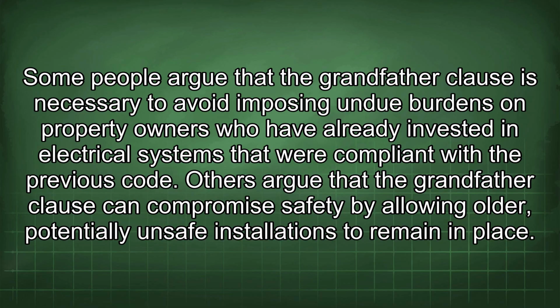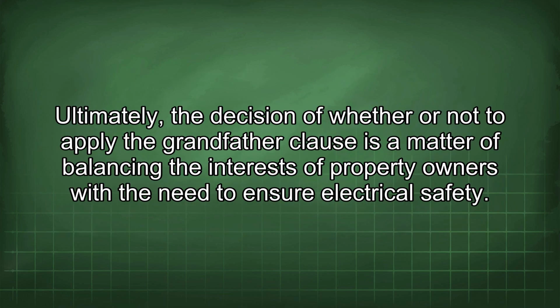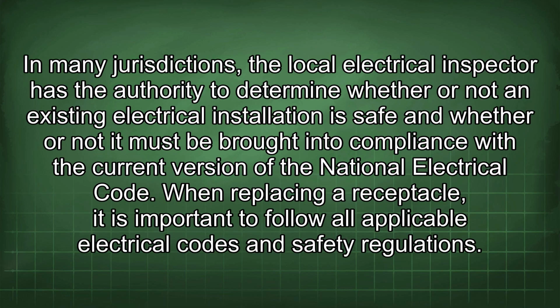Others argue that the grandfather clause can compromise safety by allowing older, potentially unsafe installations to remain in place. Ultimately, the decision of whether or not to apply the grandfather clause is a matter of balancing the interests of property owners with the need to ensure electrical safety. In many jurisdictions, the local electrical inspector has the authority to determine whether or not an existing electrical installation is safe and whether or not it must be brought into compliance with the current version of the National Electrical Code.